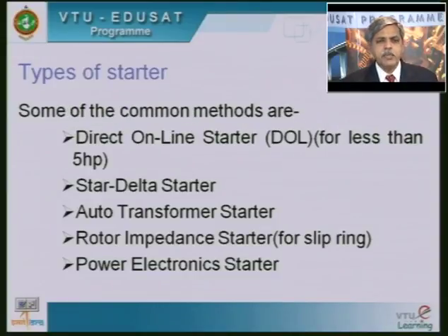So, these are the different types of starters we use for starting an induction motor. If a motor is rated less than 5 HP, I can start the motor directly online, that is called a DOL starter. Then we have a star delta starter, an auto transformer starter, a rotor impedance starter, and then power electronic starters are also there. These are all advanced starters, where here also we apply a reduced voltage at the time of starting. But these are all static devices, there won't be any moving parts.